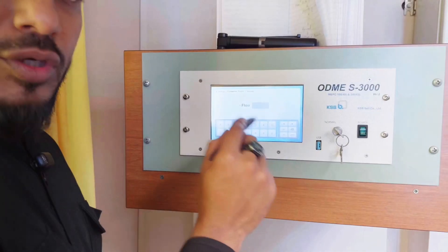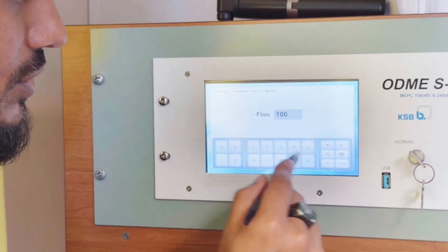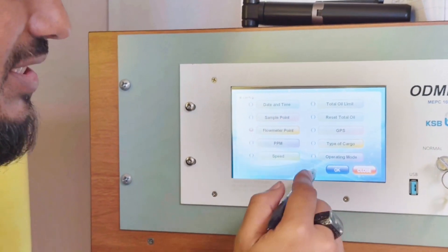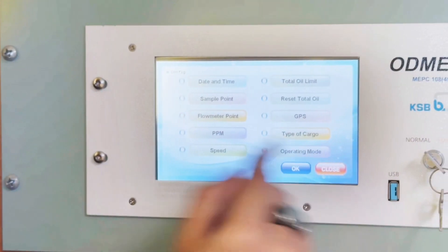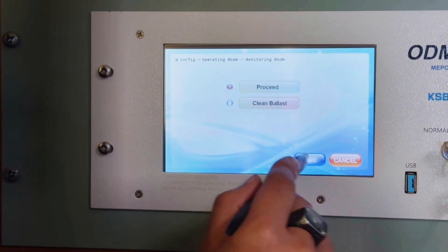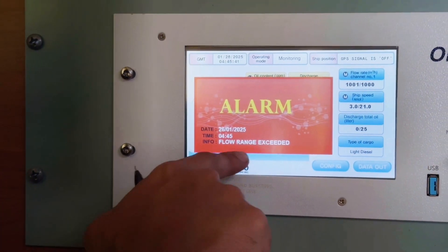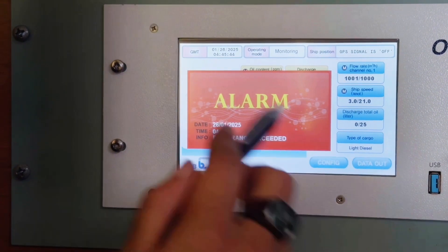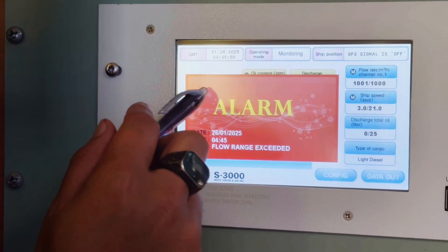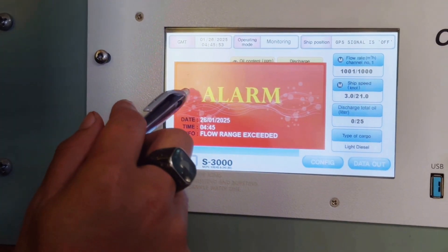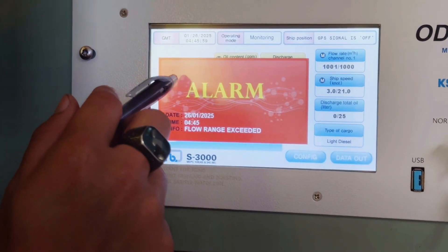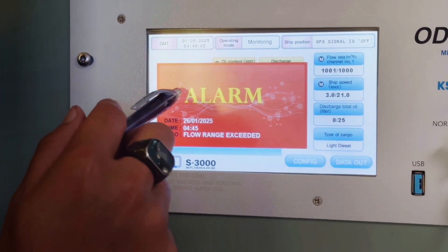Press OK and change the flow data to 1001 — that means more than 1000. Go to operating mode again, select monitoring mode, then proceed, save, and close. The alarm has come: flow exceeded the permitted value — flow range exceeded. The overboard valve will be automatically closed and discharge is prohibited. You can see it is now closed.